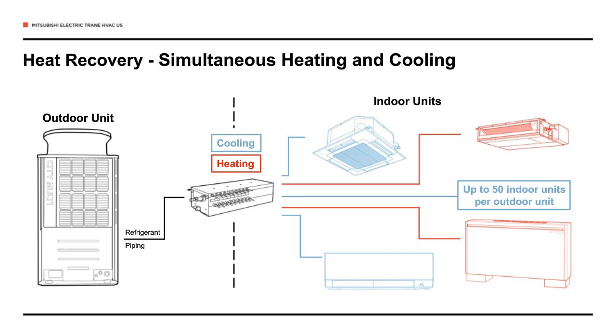These systems use a branch circuit controller to direct refrigerant based on the conditioning needs of a particular zone, either heating or cooling, as we discussed. So how does this work? Well, one way to look at the BC controller is like a quarterback or a decision maker. By using a liquid gas separator, the BC controller separates the refrigerant so that some areas are cooled and some are heated. So each area or zone has its own indoor unit that provides heating and cooling.